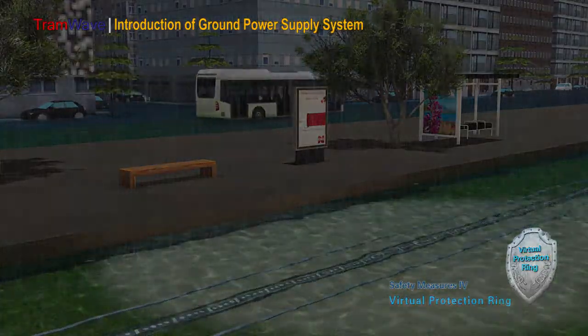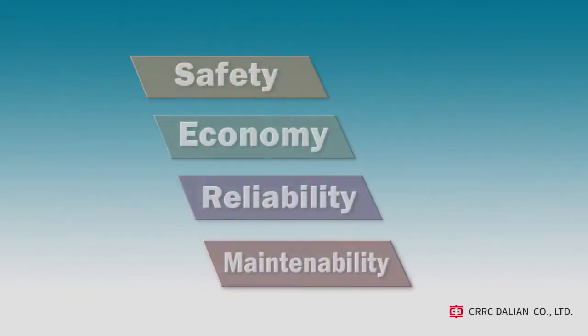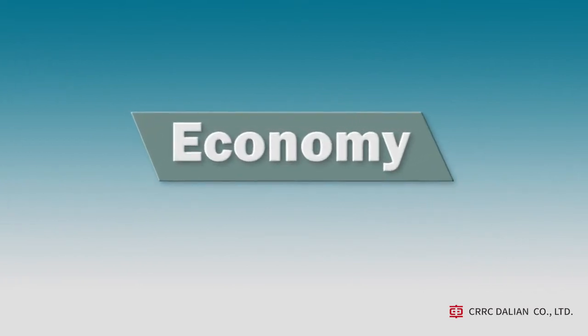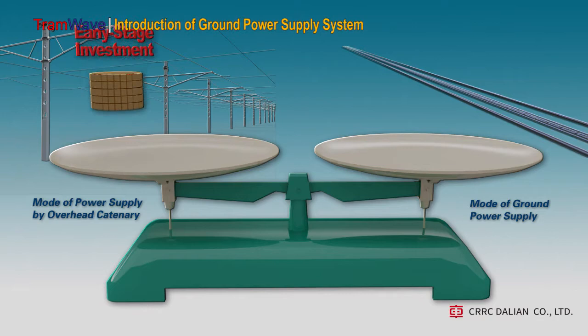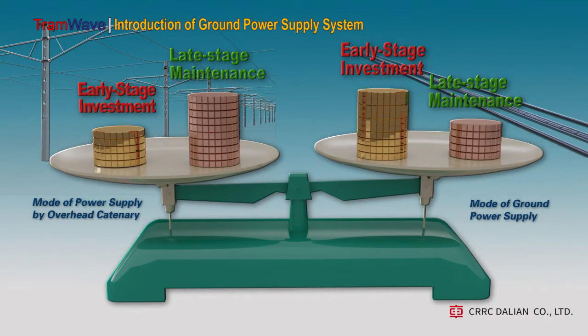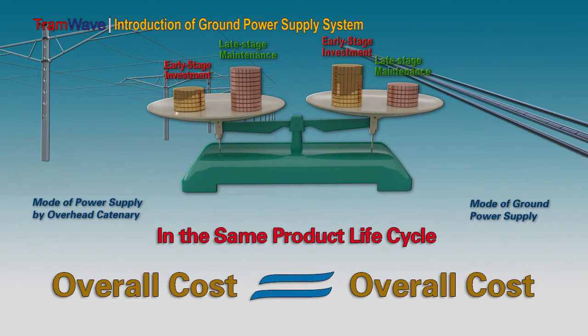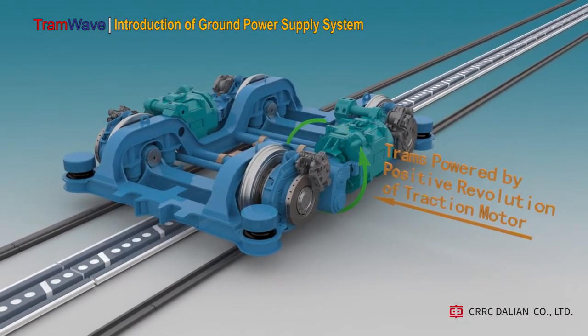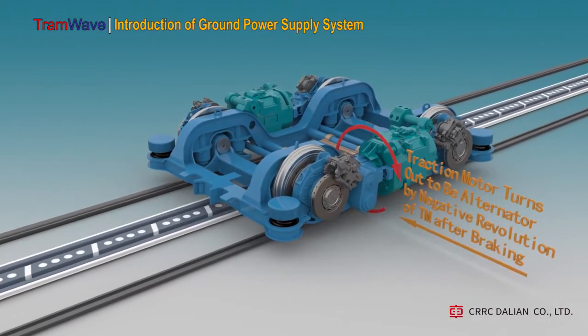The safety index of the tramway ground power supply system is certified by an Italian Independent Certification Authority with certification level SIL4. Compared with overhead catenary power supply, a larger investment is required at the early stage for the ground power supply system. However, the maintenance cost at the later stage is relatively much less, so in the same product life cycle the overall cost for both is roughly equivalent. In addition, the ground power supply system can recover a certain amount of electric energy through regenerative braking and transfer it back to the grid to save operating costs.